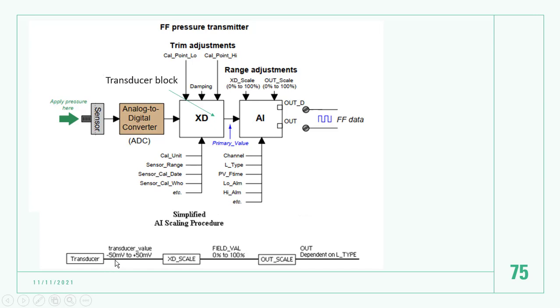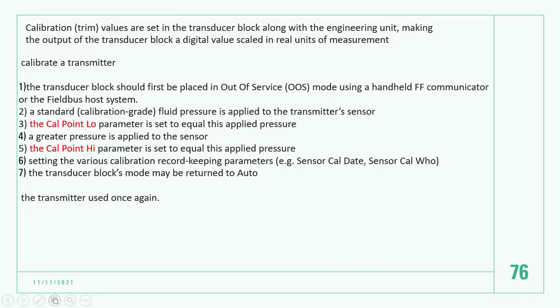Okay, the transducer range from here is, for example, minus 15 millivolts to positive 15 millivolts. If your calibration is 0 to 100 feet of water, okay, this goes to the output. Calibration is called trim. When you are setting the transducer block along with the engineering unit, you make the output of the transducer block a digital value, scaled in real units of measurement.